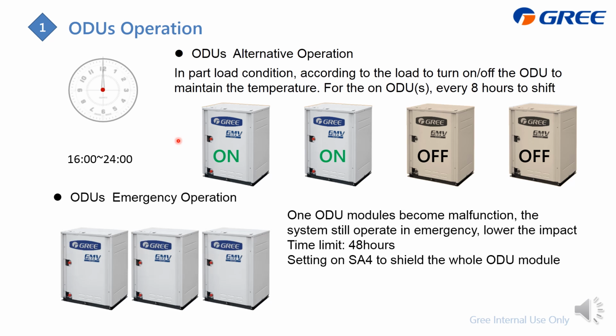And also the outdoor unit emergency operation is the same, which means if there are 3 outdoor units in the system and this one malfunctions, we can set this switch on the control board to emergency operation to allow the system to continue operating, but the time limit is 48 hours.